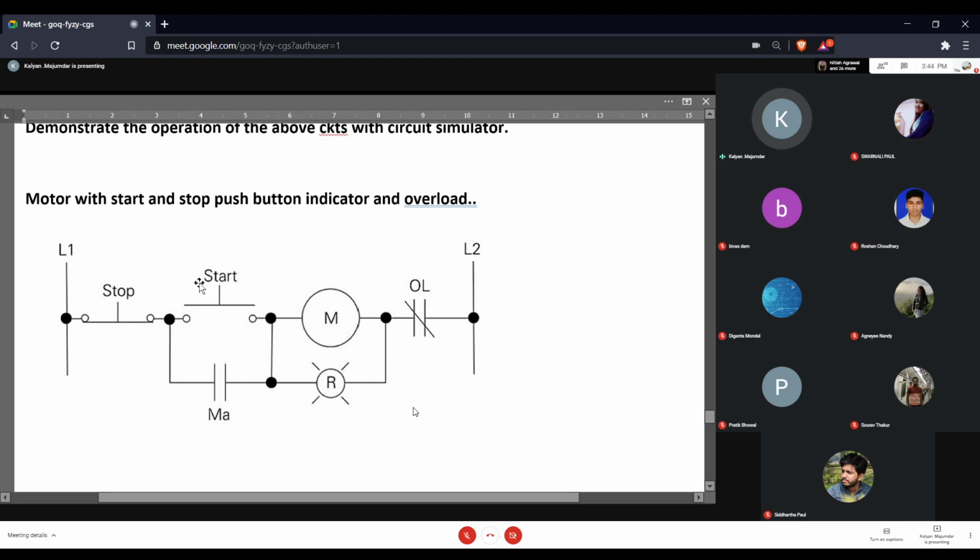তাহলে এবার কি হচ্ছে, when you press the start button, power flows into the relay coil. It's still not overload situation, still the current is well within safe limits. So the current is flowing, the relay is energized. When the relay becomes energized, this contact closes. So you have a parallel path across the start push button. Now, if you release the push button, what happens is the circuit is now maintained along this particular path. The relay remains closed. The motor keeps rotating until and unless you press the stop button.